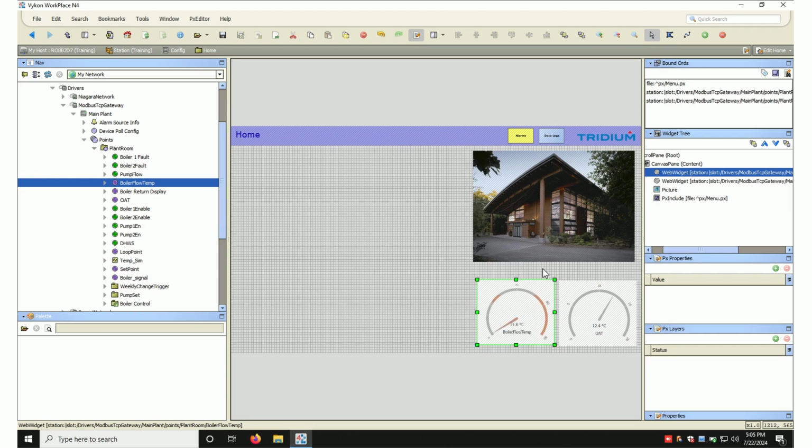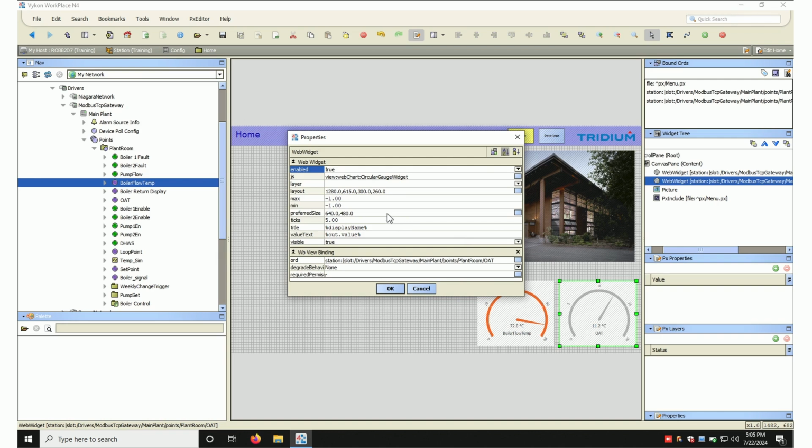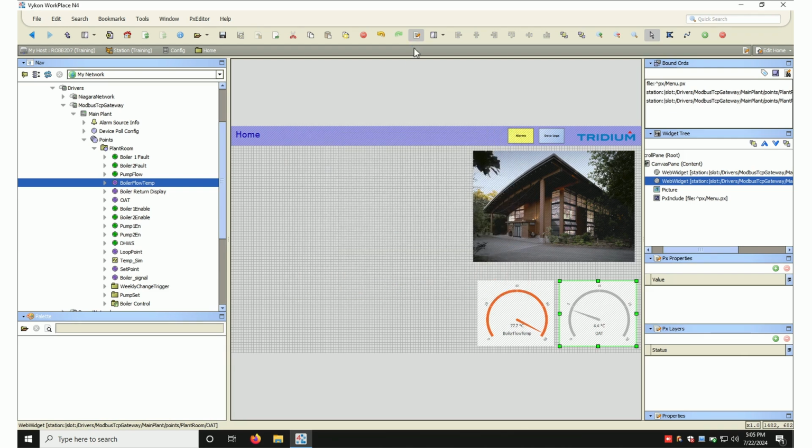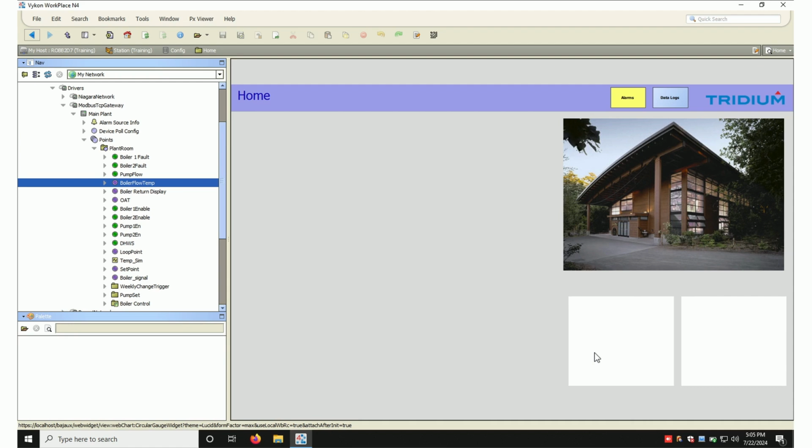Now, these gauges, you can't adjust them in any way, in that if I want it to be between 0 and 10, it's blue, 10 and 20, it's orange, 20 and 30, it's red. Unfortunately, they're a very, very basic component. You can't manipulate the colour bands. What it will do is change colour based on the source point status. So we can see it's orange because it's in fault. It'll turn red when it's in alarm, purple for an override, and so on.